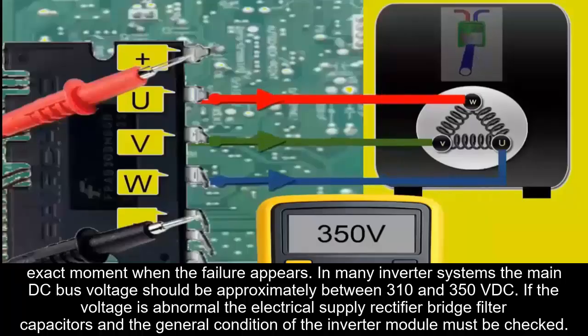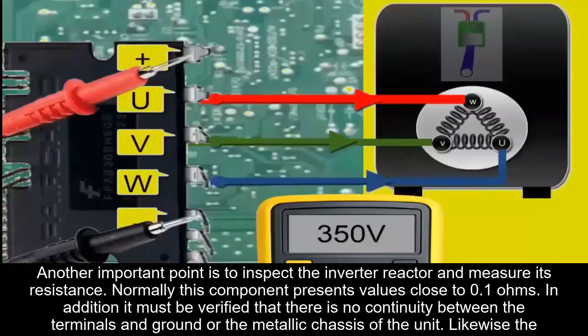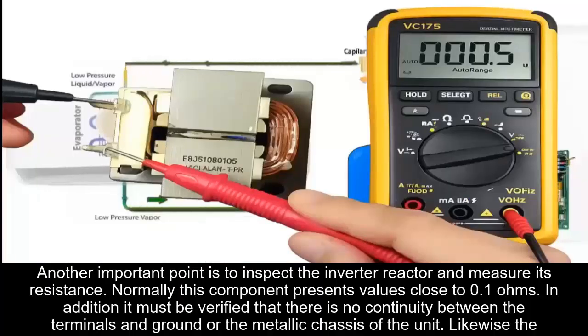If the voltage is abnormal, the electrical supply, rectifier bridge, filter capacitors, and the general condition of the inverter module must be checked. Another important point is to inspect the inverter reactor and measure its resistance. Normally, this component presents values close to 0.1 ohms. In addition, it must be verified that there is no continuity between the terminals and ground or the metallic chassis of the unit.